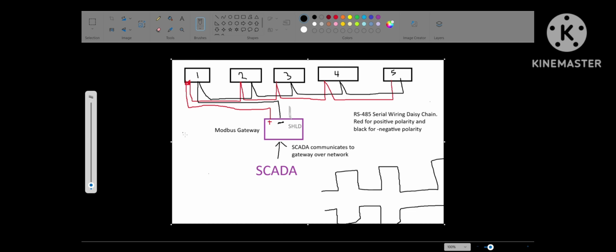Anytime you're looking at EPMS, BMS devices these days, depending on the vendor, most of the time it's going to be Modbus. They may use SNMP. They also may use BACnet. There's different options, but in this case, we're going to focus on Modbus. So in general, how Modbus works, in this scenario, this is a Modbus RTU network.